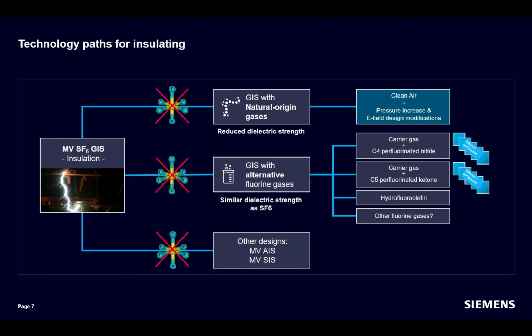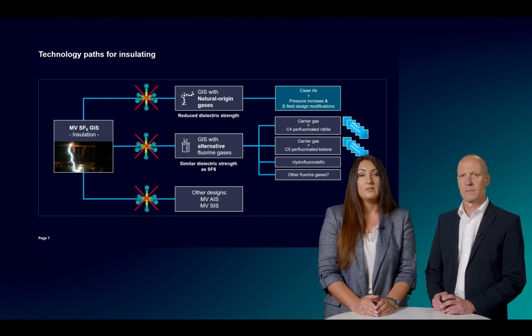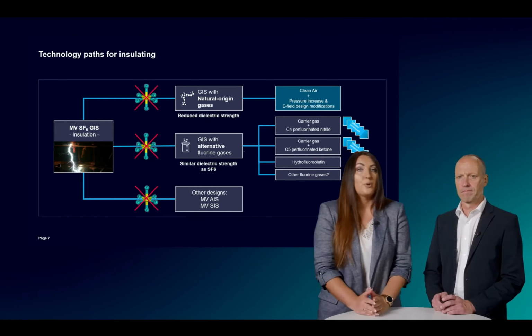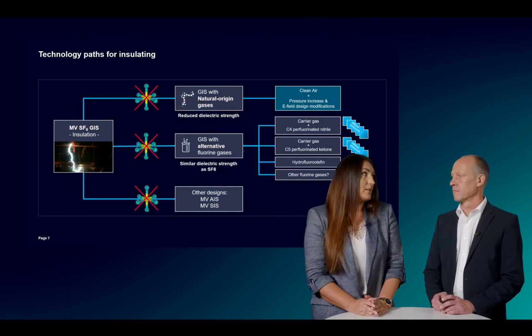So, technology paths, if we talk about the insulation, were either to choose between natural origin gases with reduced dielectric strength, or alternative fluorine gases with dielectric strength somewhat similar to SF6. And the third path would be a completely different technology, as, for example, air-insulated switchgear or switchgear with solid insulation. So Siemens decided to choose the path with clean air, using only natural origin gases with increased pressure and then a modified design of the electrical field. And if you look back to the European F-gas ban, it was certainly the right decision.